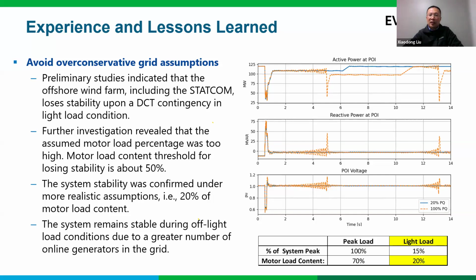So what happened was that in our previous studies, the load was assumed to be constant PQ load. We know that represents 100% motor load. As shown in the diagram on the right, the system is unstable at 100% PQ load. So our previous studies and assumption were just too conservative and unrealistic. So we had to go back, restudy, and correct the previous study result, and the system showed stable at 20% PQ load under all contingencies. All right, that's all I have today for the grid forming STATCOM.